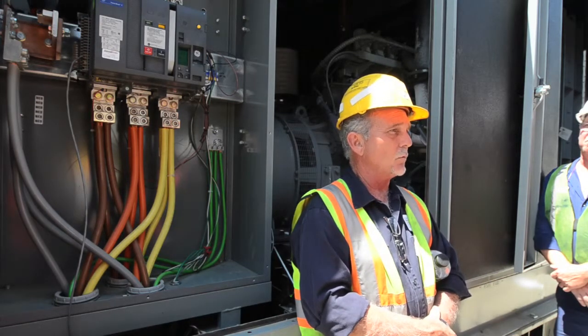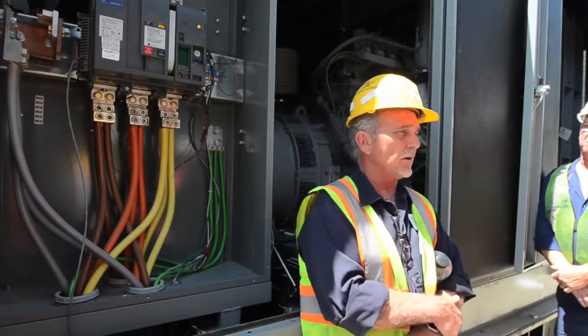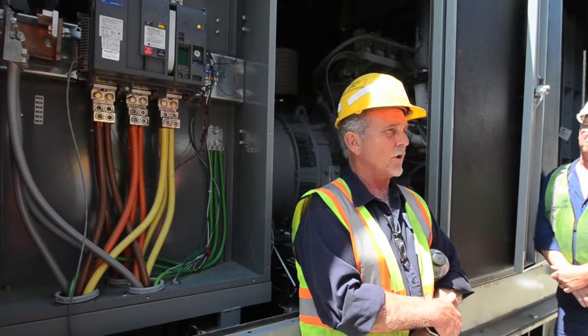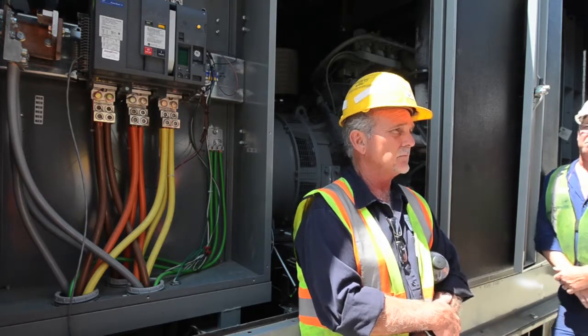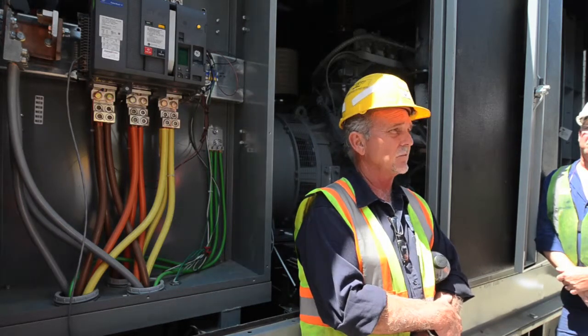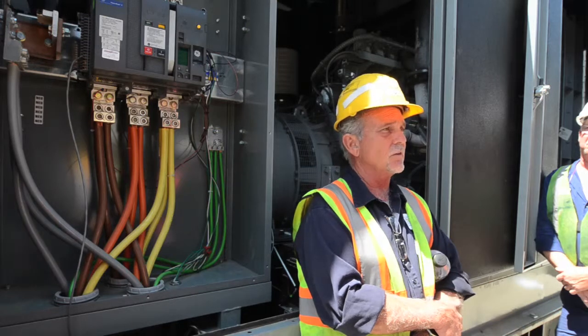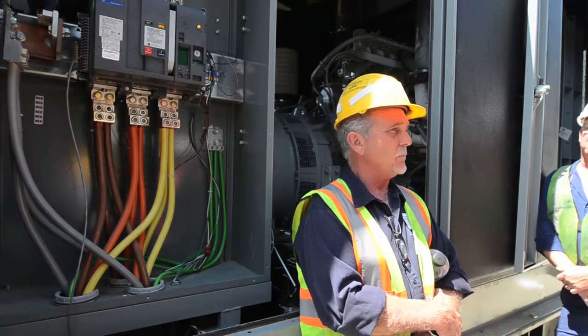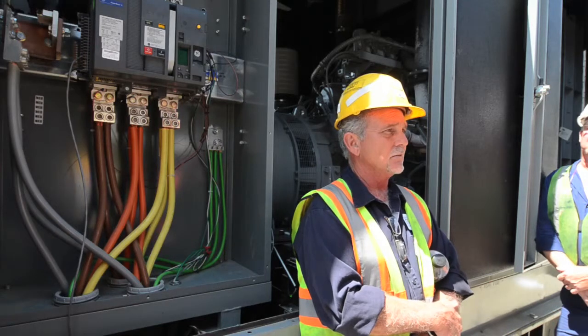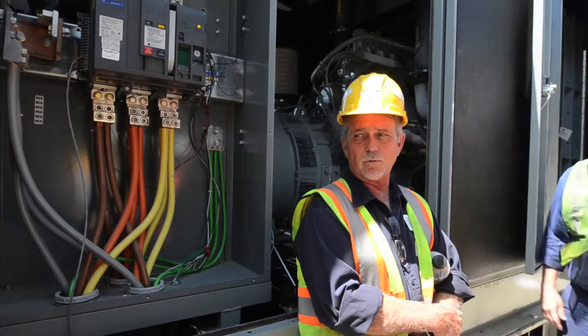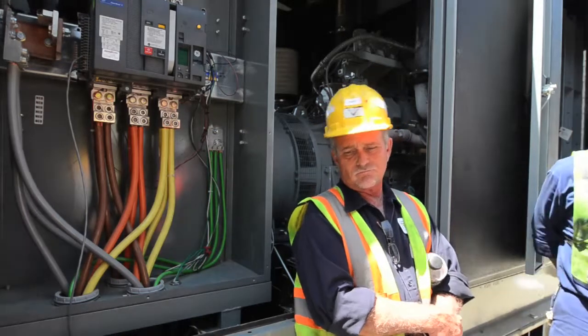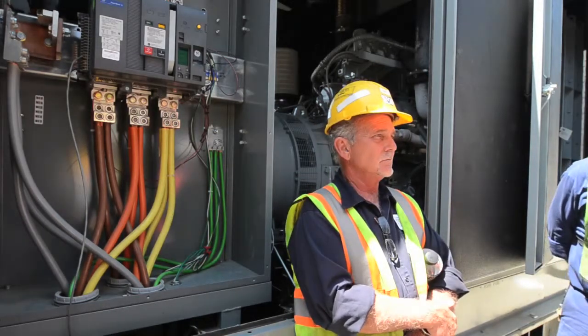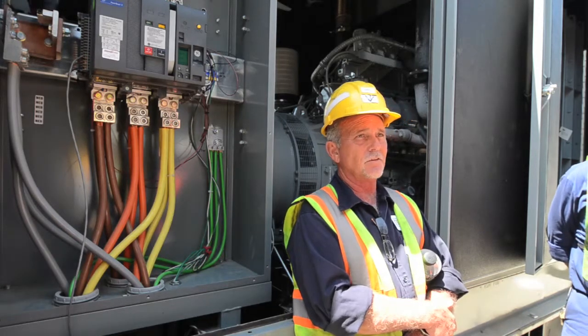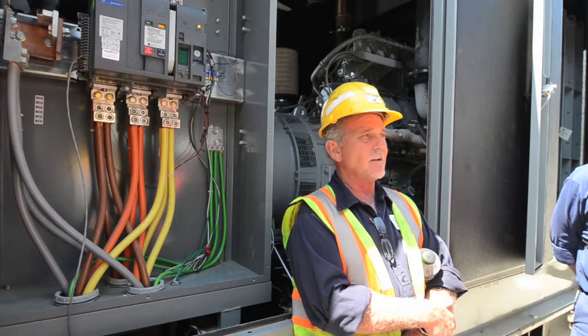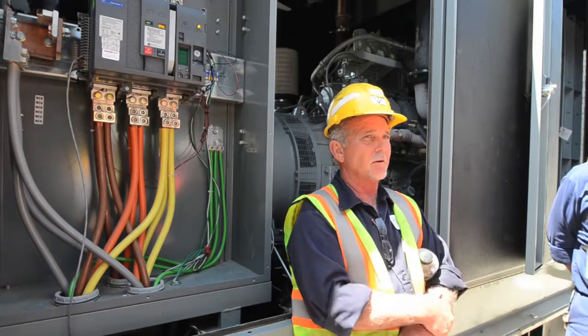You can't put a 1.3 megawatt in here because one set of leads is not capable of carrying that rated load. So the maximum rental you could ever bring in and tie in up here would be 650. Now on the bus downstairs, you can bring in a 2 megawatt. Because you're tying to the bus. So there's lots of things that can be done. The only thing is, I'd hate to be the guy that had to pull the cables down underground. Because even on a 1.3 meg, you would be bringing in 5 cables per phase. And you'd be, that's 15, 16, 17, 18. That's 19 cables that you would have to drag from up here somehow to get down into that room.